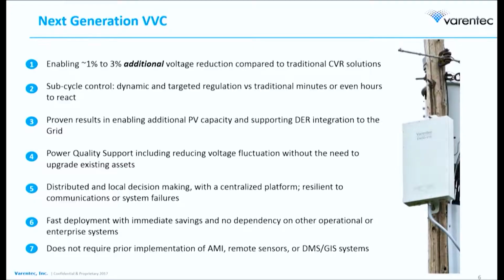So to summarize what the next generation VVC is: this is power electronics equipment that we put on the secondary side of a distribution transformer. Throughout the projects we've done, we found it enables an additional 1 to 3% of energy savings on top of what has typically been accomplished with traditional CVR systems.